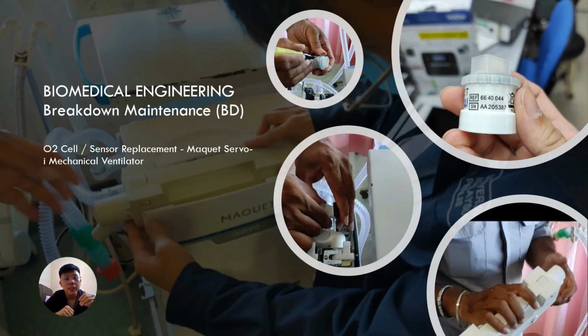So for the first step of the replacement of the oxygen sensor, we need to put the new sensor under the sun for 5 minutes. After that, we need to label the new oxygen sensor. Then we can remove the old oxygen sensor from the patient unit. In order to remove the old oxygen cell from the patient unit, we need to remove the expiratory cassette. We will remove the expiratory cassette and install a new oxygen cell into the mechanical ventilator. After that, we will close it up with the expiratory cassette. After that, we need to perform the pre-use check to check whether the O2 cell is at 100% or not.